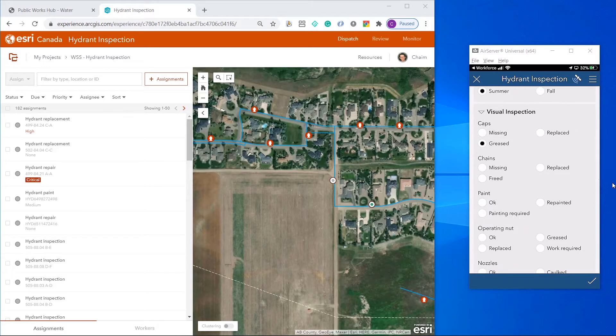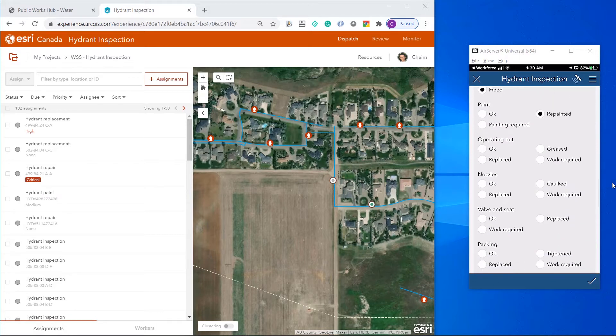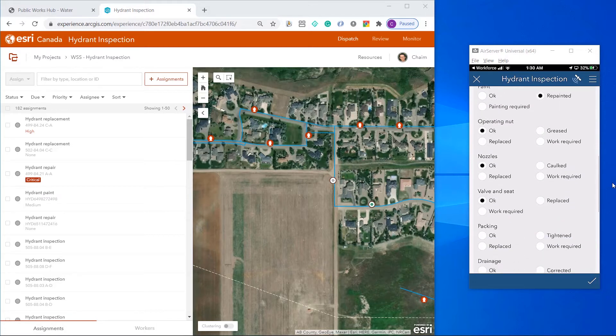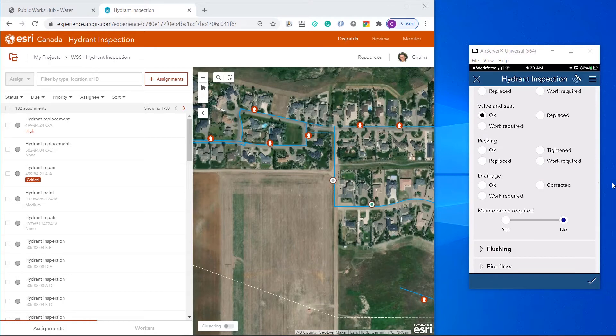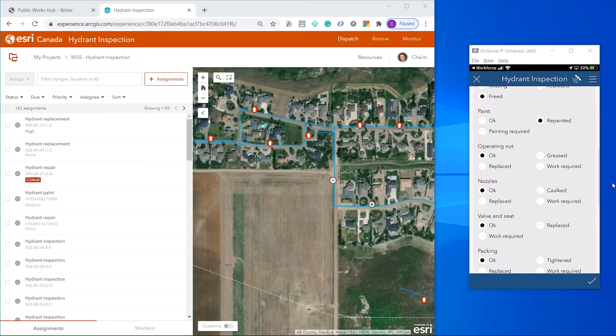Caps have been greased. Chains have been freed. Hydrant has been repainted. Operating nut, okay. Nozzles, okay. Valve and Seat, okay. Packing and drainage are okay. So no maintenance is required.